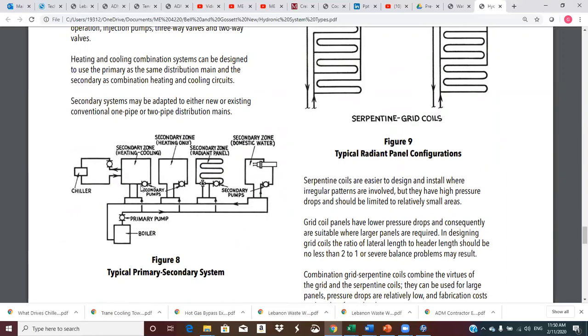Likewise, if we don't run this pump, we can run a pump over here and put chill water up into this loop as well, and we could still use this pump to circulate. So this secondary zone can heat or cool because of the chiller. This one is heating only. Again, when this pump runs, it pulls hot water out of the primary loop through the secondary and then returns it. This could be underfloor or radiant panel, and this could be domestic hot water. We're going to spend a bunch of time on that, so I'm not going to spend too much on it right now.